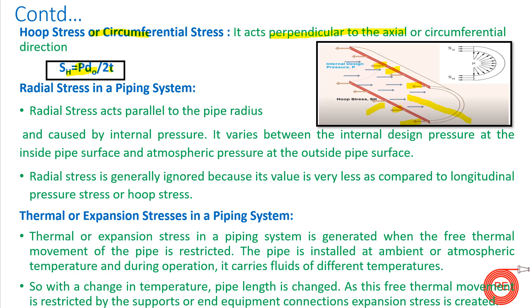Hoop stress and longitudinal stress are the two basic stresses mainly responsible for piping deformation. Radial stress, by contrast, is generally not taken into account during piping stress analysis. Radial stress acts parallel to the pipe radius and is caused by internal pressure. It varies between the internal design pressure at the inside pipe wall and atmospheric pressure at the outside surface. Its value is very small compared to longitudinal or hoop stress, so most designers neglect it.